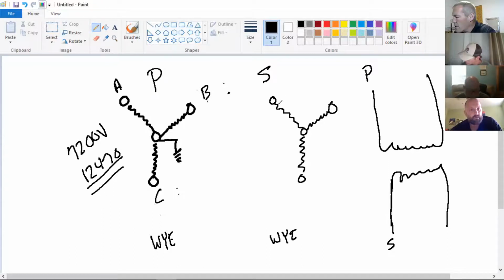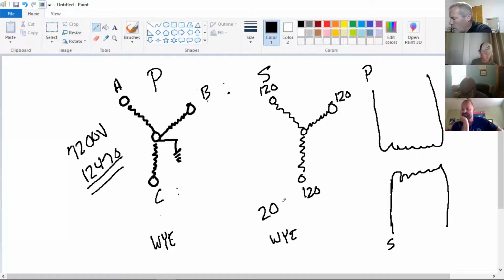In transformation, if my output voltage is 120, what is my phase to phase voltage on the secondary side? I'll wait on this one. If you're having difficulties, look at figure 1210. 207.9, you're right, round it. 208 volts. So this applies to any time that you have three-phase power, both in primary and secondary transformation.